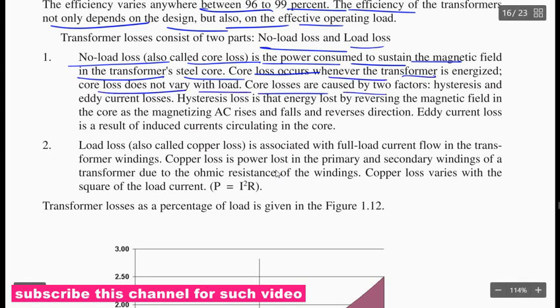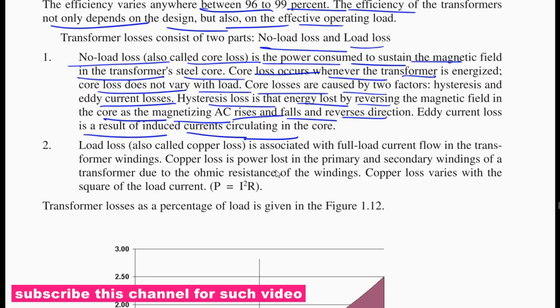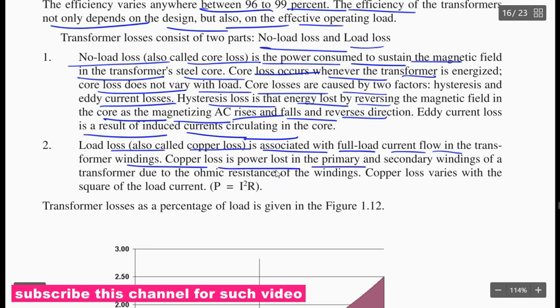Core losses are caused by two factors: hysteresis and eddy current losses. Hysteresis loss is energy lost by reversing the magnetic field in the core as the magnetizing AC rises and falls in the reverse direction. Eddy current loss is a result of induced current circulating in the core. Load losses, also called copper losses, are associated with the full load current flow in the transformer winding. Copper losses are power loss in the primary and secondary winding of the transformer due to the ohmic resistance of the winding. Copper losses vary with the square of the load current, P equals I squared R.